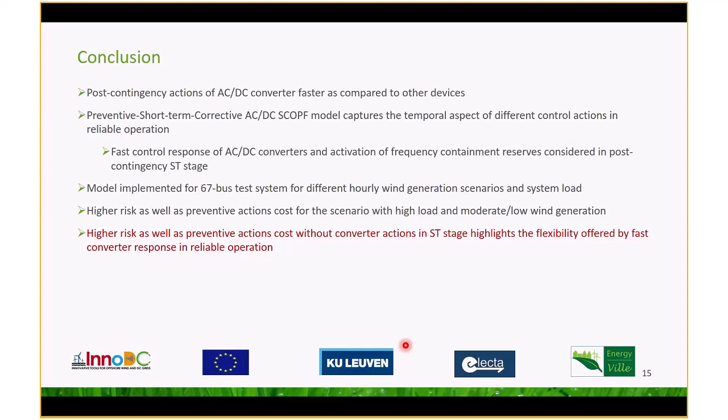It was seen that there is higher risk as well as preventive actions cost for the scenario with high load and moderate or low wind generation. It was also seen that without converter actions in the short-term stage, there is a higher risk and preventive actions cost. This highlights the flexibility offered by the fast converter response in reliable operation.